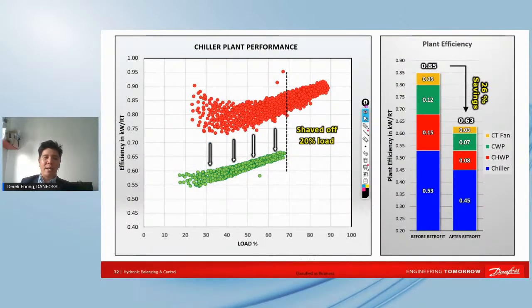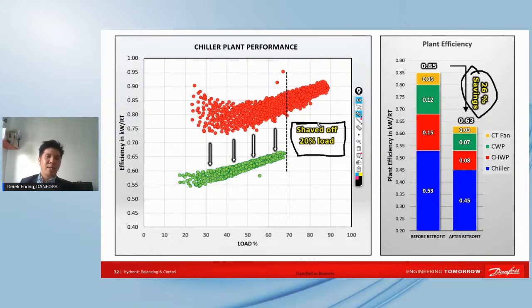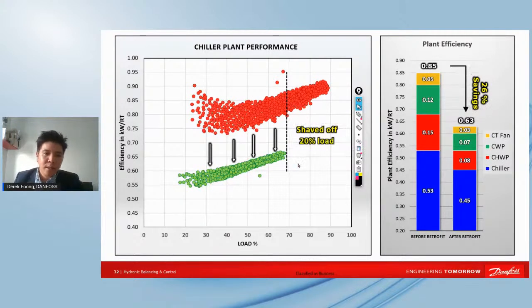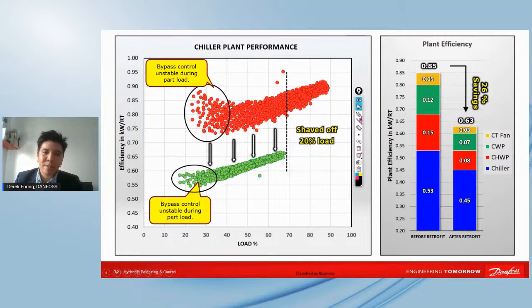So now, what is the main result of the entire system impact? We do not just see numbers on the kilowatt per ton: we get to reduce 26% overall, with all the heavy equipment stacked together. But we look at the entire plant characteristic, which is the sum of all the heavy equipment here. So besides the active energy saving of 26%, we also see a maximum demand reduction of 20%. So there's a lot of money there. And what is more important in this characteristic is that the chiller plant is also very stable during part load.